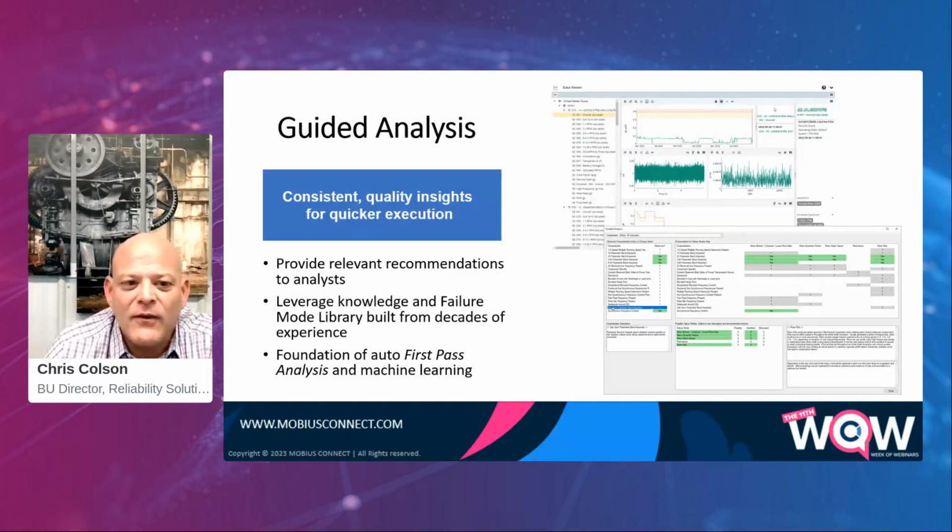Now, once the analyst has this in front of them, they then will review the data surrounding the issue. And as the analyst reviews this data, they may select the observed characteristics. Maybe they're looking at two time RPM, and it's the elevated noise floor. Possible failure modes are selected based on the identified characteristics of what they see. And then the analysis, along with the analyst that's now looking at it, decides which failure modes to include, and text for the assessment is generated for the analyst to review and to edit, maybe make modifications to it. But it's a much faster, quicker way of using the algorithms that have been built, using the failure modes that have already been defined and put into a library to drive a more tailored and more accurate fault entry and repair recommendation for our customers.